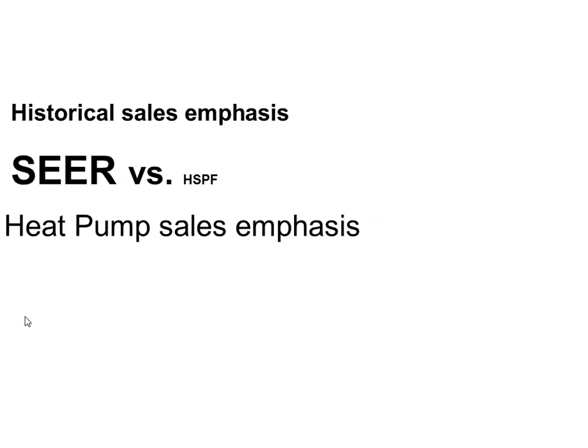All right, so HSPF, heating seasonal performance factors, how air source heat pumps are rated in the 1 through 5-ton residential size category range. Even if it's a commercial job, it's still a residential heat pump you'd be putting on it. Traditionally, we've always talked about heat pumps in terms of SEER, just because we're used to that from the air conditioning world. However, SEER is an incorrect term. SEER has never applied to heat pumps ever.